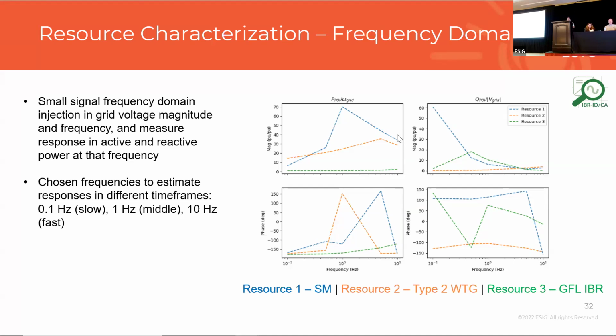So on this side of the frequency trace, we see that the type 2 wind and the synchronous machine have more response for per unit change of frequency as compared to the inverter. And the cursor just went away. Okay, as compared to the inverter, the synchronous machine has more response in the middle frequency region. In the lower frequency region, they all kind of start tapering out.